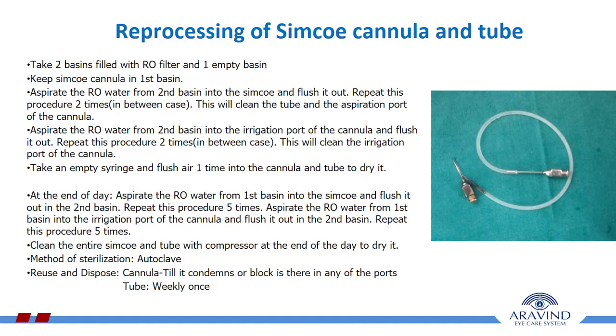Reprocessing of Simcoe cannula and the tube. Take 2 basins filled with RO filter water and 1 empty basin. Keep the Simcoe cannula in the first basin. Aspirate RO water from the second basin into the Simcoe and flush it out. Repeat this procedure 2 times in between cases. This will clean the tube and the aspiration port of the cannula.